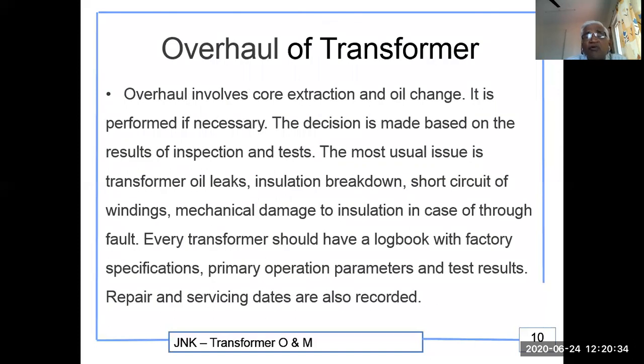Overhaul of the transformer, that is, core extraction and oil change, is performed if necessary. The decision is made based on the results of the inspection and tests. Many times you will not be able to do it at your site. The most usual issues are transformer oil leaks, insulation breakdown, short circuit of the windings, and mechanical damage to the insulation in case of through faults. Every transformer should have a logbook with factory specifications, primary operation parameters, and test results. Repair and servicing dates are also recorded in the book.